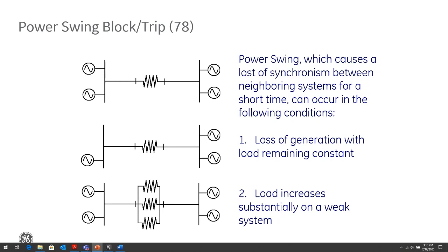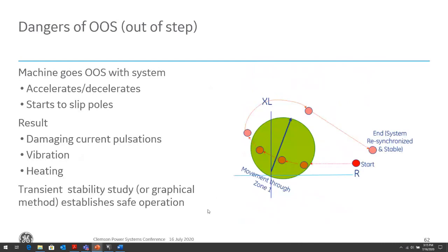So if that power swing, or what we call the electrical center of that power swing, swings into our GSU or a generator, that can cause the generator protection to either see that as a fault, or if it's an unstable power swing, we need to trip that generator. So we might need to block, or we might need to trip. For a stable power swing, we might need to block protection that can be susceptible to misoperation for that power swing. And if it's an unstable power swing, we need to be able to trip the machine to prevent damage to the machine.